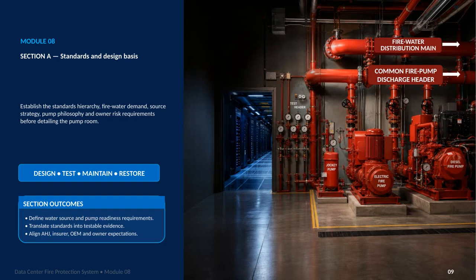Before we detail the pump room, we need to establish the governing standards hierarchy, determine the required fire water demand, define the water source strategy, agree on the pump philosophy, and understand the owner's risk requirements. The key principle is to design, test, maintain, and restore the system as one continuous life cycle, not as separate activities. In this section, I'll focus on 4 outcomes.